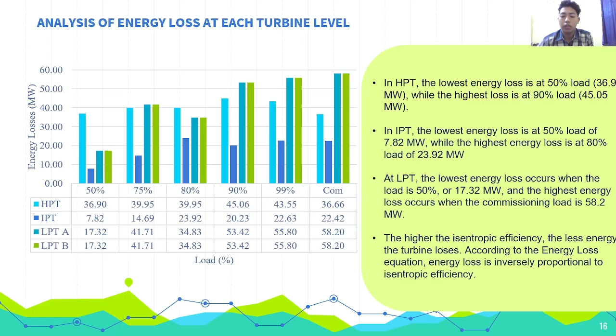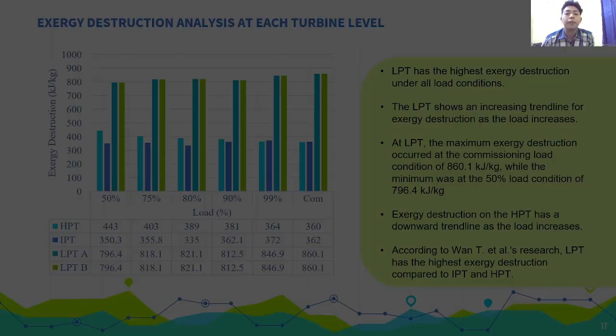Analysis of energy loss at each turbine level. In the high pressure turbine, the lowest energy loss is at 50% load, while the highest loss is at 90% load. In the intermediate pressure turbine, the lowest energy loss is at 50% load, while the highest energy loss is at 80% load. At the low pressure turbine, the lowest energy loss occurs when the load is 50%, and the highest energy loss occurs at the commissioning load with a value of 58.2 megawatt. The higher the isentropic efficiency, the less the energy loss. According to the energy loss equation, energy loss is inversely proportional to isentropic efficiency.